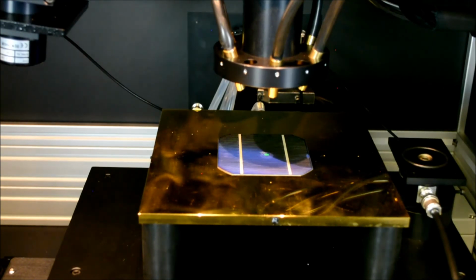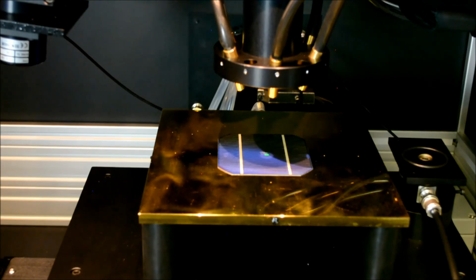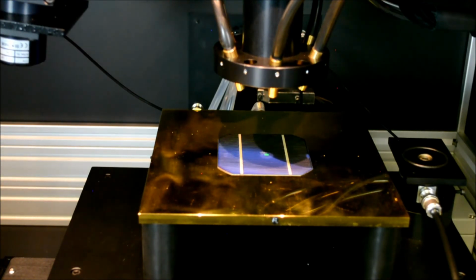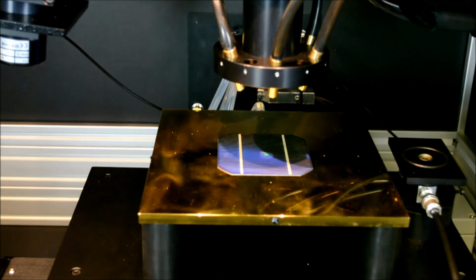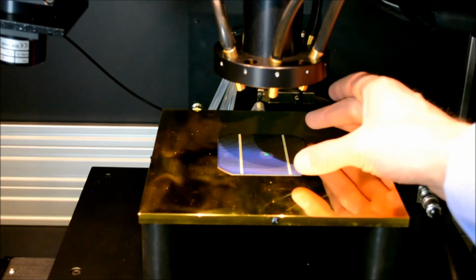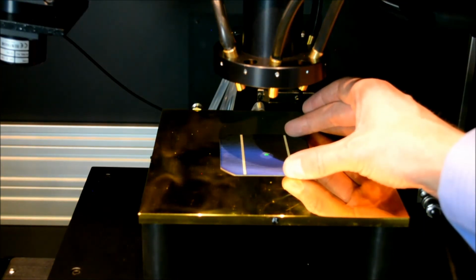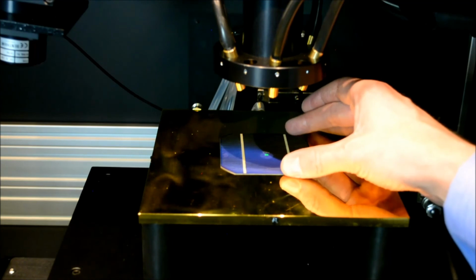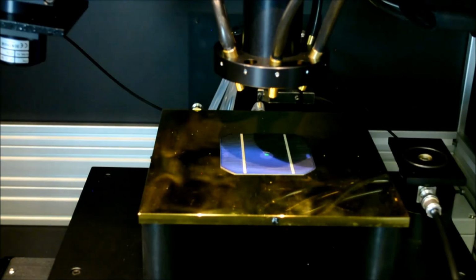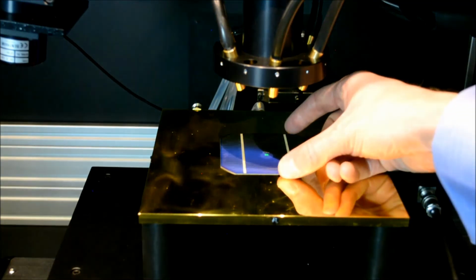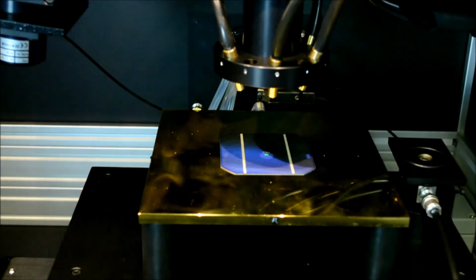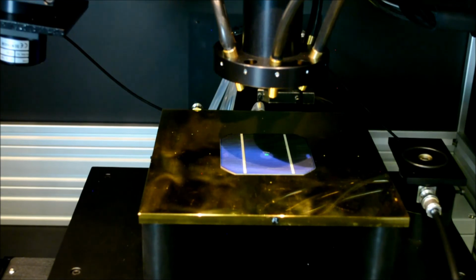Now we will set up our device under test to measure its spectral responsivity. First, I will illuminate the VCTE20 unit and switch on the vacuum supply to hold the sample in place. And we should position the sample in such a manner that the monochromatic probe is not illuminating either the electrodes or the fingers of the device.